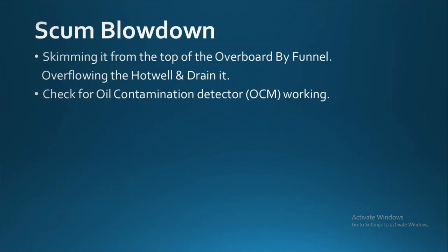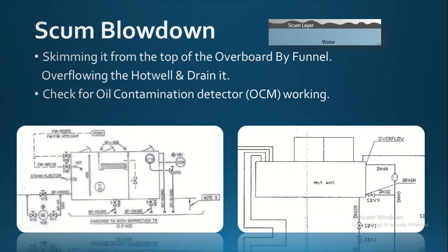The next action we have to take is to do the scum blowdown. We have to perform the scum blowdown by skimming it from the top, overflowing the hot well, and then draining the scum. As you can see on the right figure, there is an overflow line, and on the left, there is a funnel provided to collect the scum. We have to check for the oil contamination monitor (OCM), which gives an alarm if any kind of oil is entering the hot well.